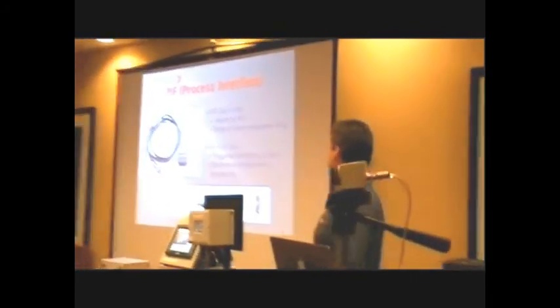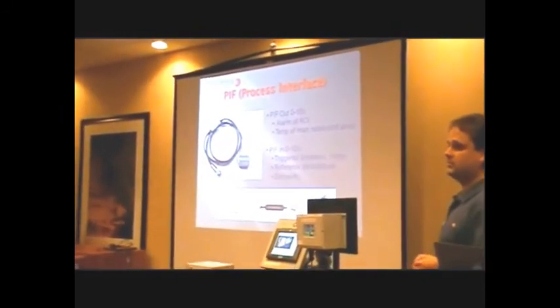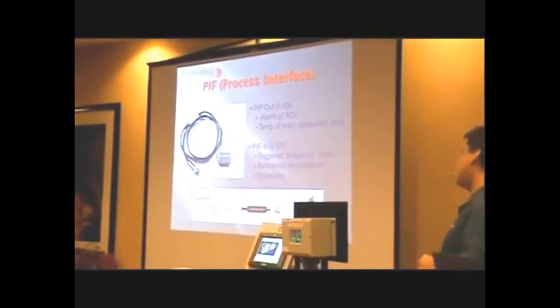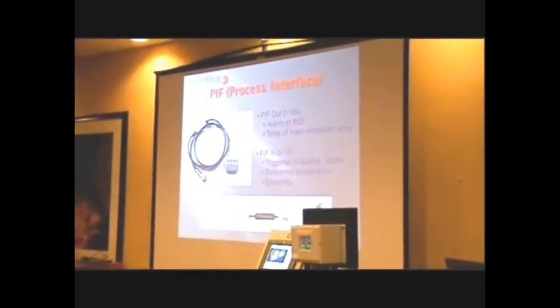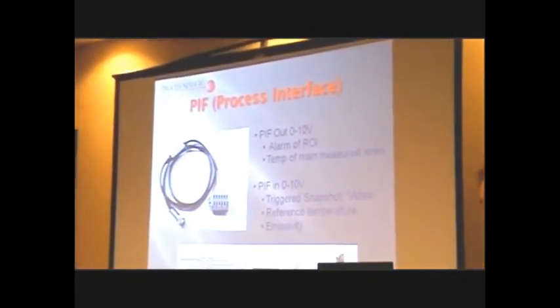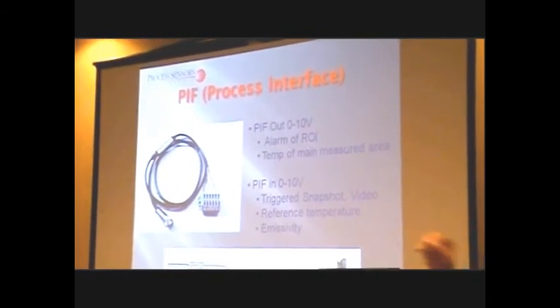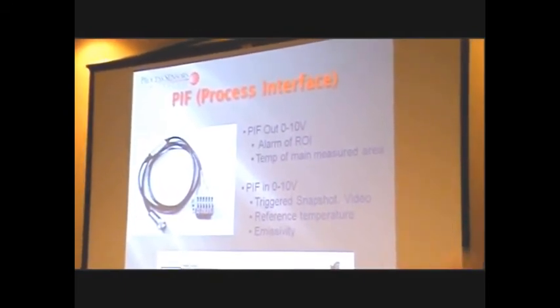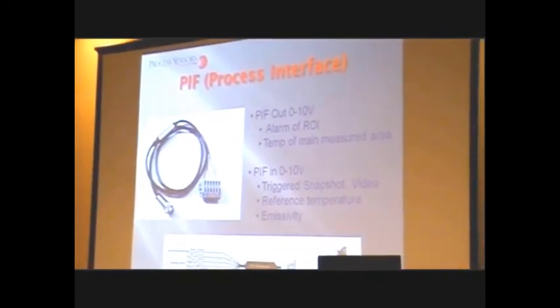The PIF in, yet again, uses the zero to ten. We can trigger a snapshot. That's an image from the camera itself that's running on a computer. We can also activate a sequence of video. So if you had an alarm event, you could... let me rephrase that. If you had a kiln, for instance, you could send in a proximity switch signal that basically starts an image which starts the rotation of the image of the actual kiln itself. So you could actually get a full video of the complete rotation.